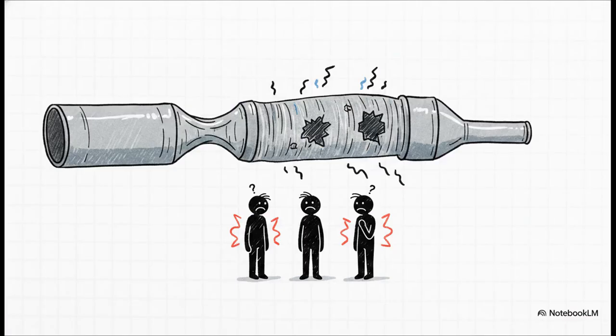Now, that delivery truck can be stopped by several hidden physical roadblocks. We're talking severely undersized ducts trying to push way too much air, collapsed flexible lines acting like a kinked garden hose, leaky ductwork just spilling cold air into the attic, or improperly adjusted VAV boxes, which are really just the dampers that control the air volume to specific rooms.